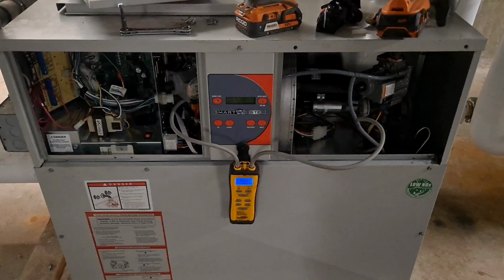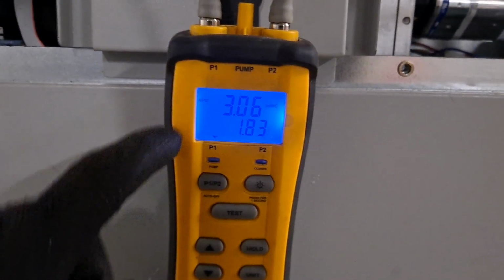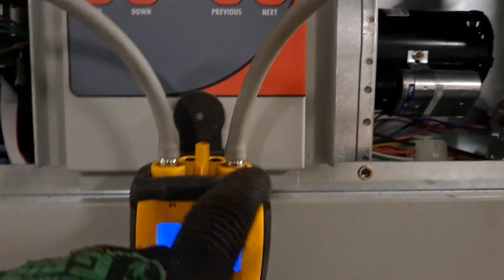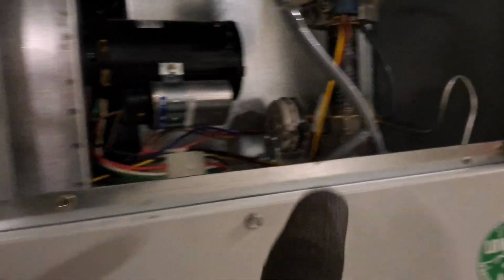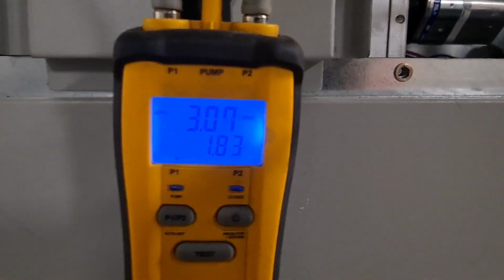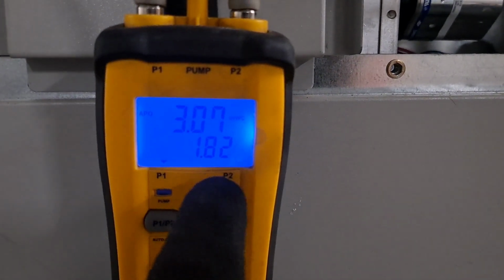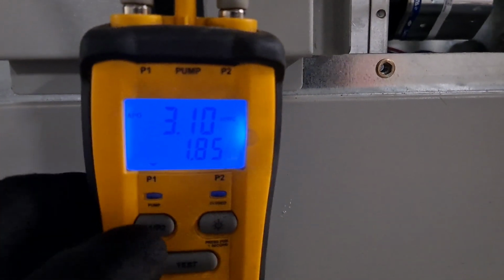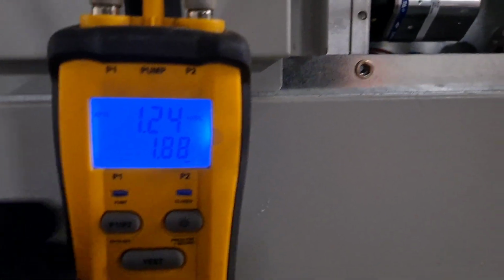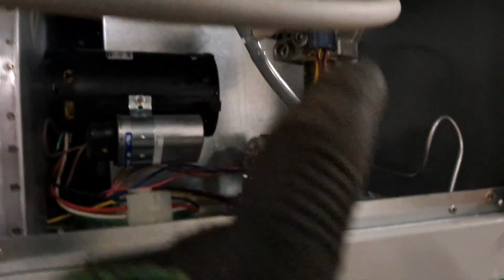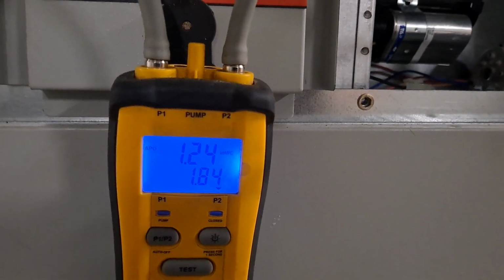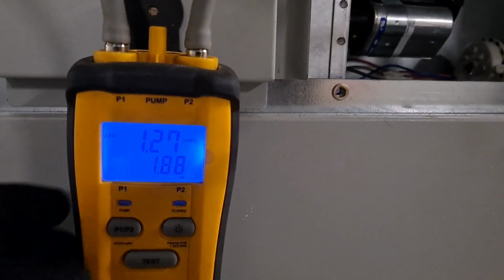Happy HVACing, and Happy New Year to everyone. So you can see here, this 3 inches is over on my gas valve side, but again, since I'm hooked in over here, I'm looking for differential pressure, and it's supposed to be 1.8 inches, and that is my differential pressure, because there we go. So I'm at 1.2 inches over here, going down into the chamber. And it was calling between 1.2 and 1.3, so I'd say that's perfect.